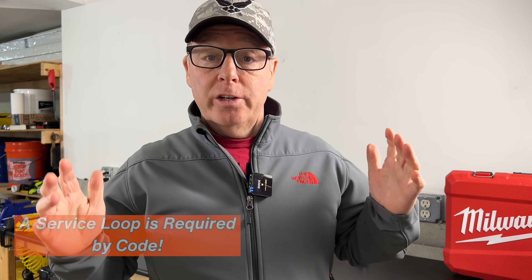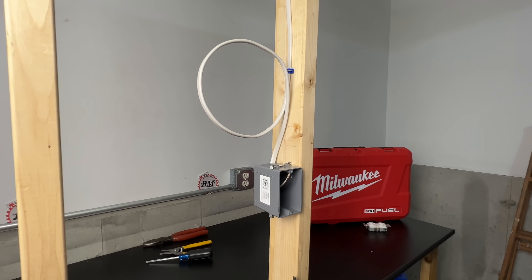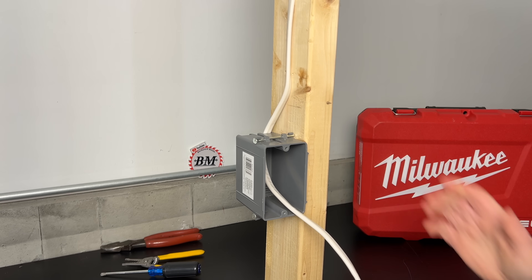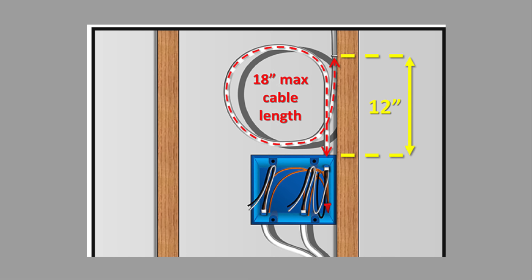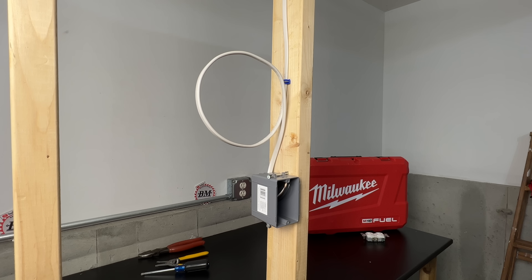False claim number four: a service loop is required by code. A service loop is the extra cable left just outside outlet boxes in case something has to be moved, the wires are damaged during construction, or they get cut short over the years. That extra slack can then be pulled into the box rather than having to extend the wires or run new cable. This is not a bad idea, but it isn't required by code and can actually be a code violation. Article 334.30 tells us that cable requires support within 12 inches of the box, and also within 18 inches of the cable length. This limits the extra cable to just six inches between the staple or last support and the box. Larger loops will not pass inspection, so service loops are optional but not required by code.